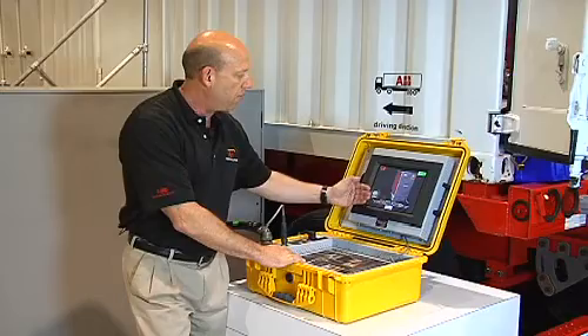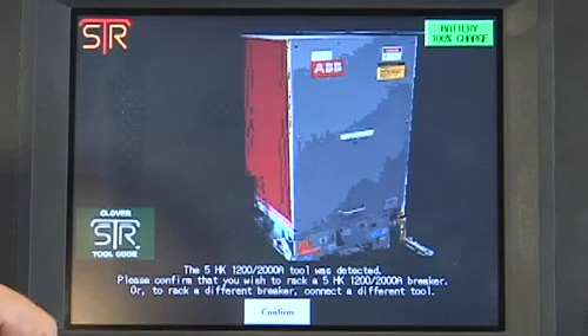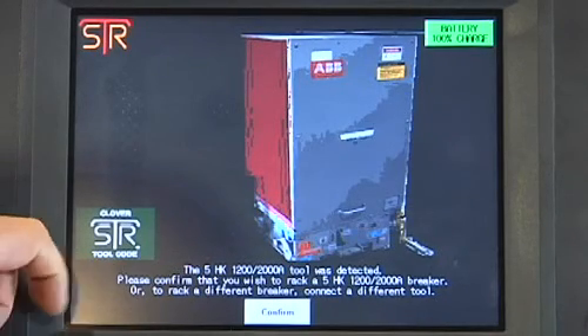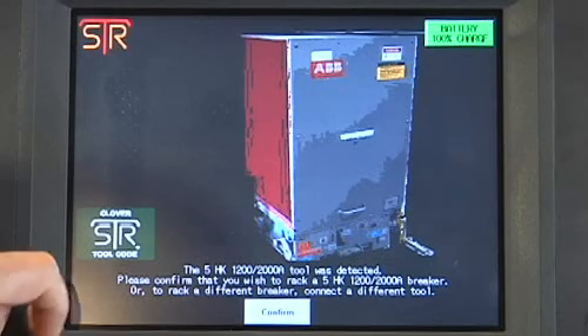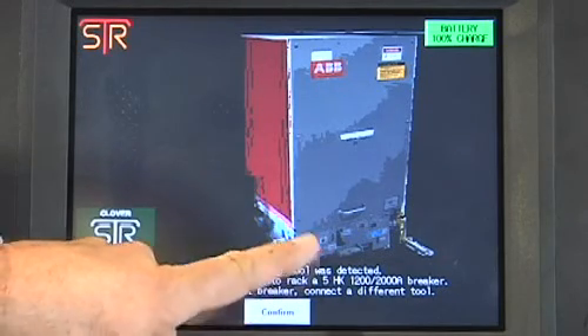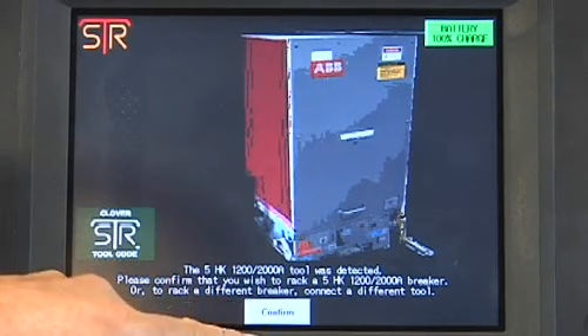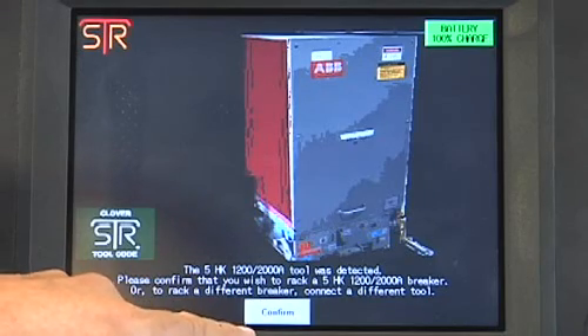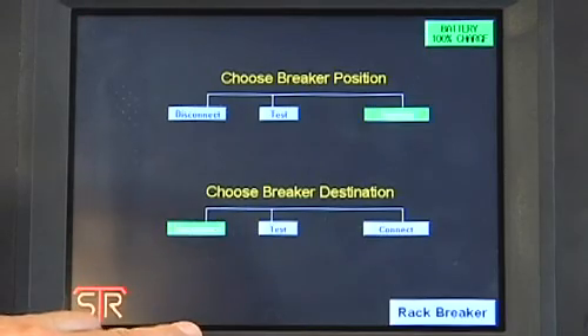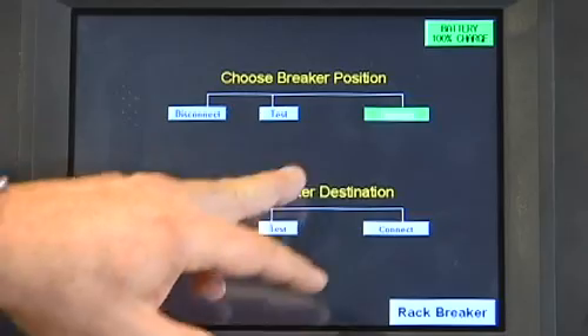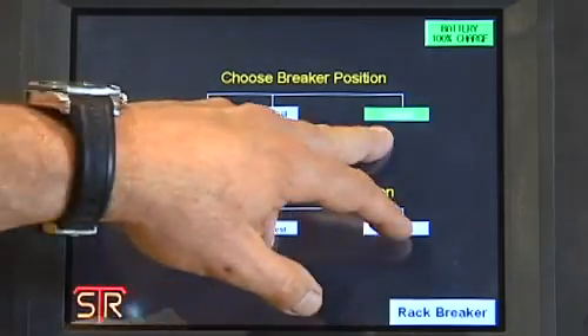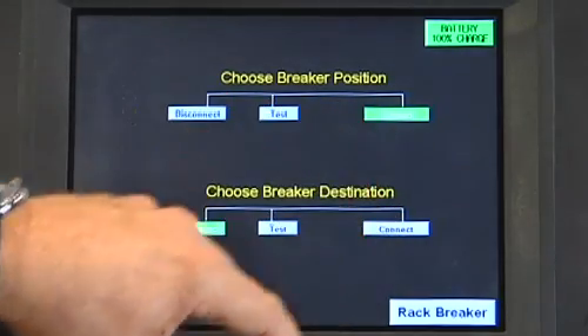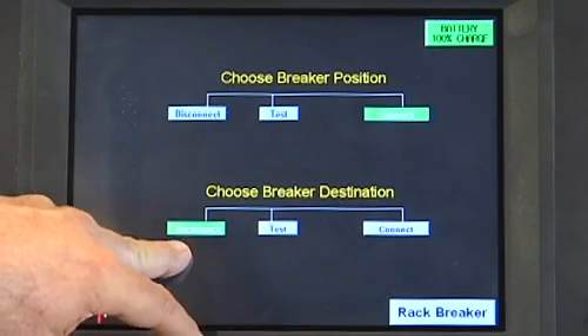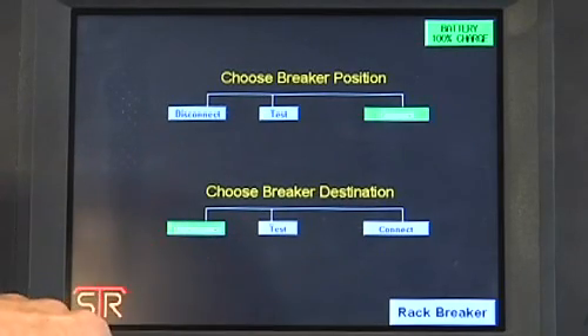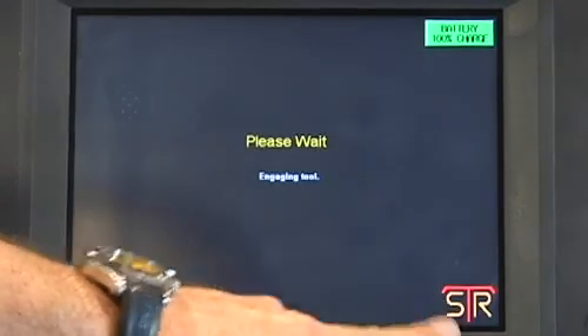Once we've confirmed that, it brings us to the screen acknowledging that we have connected the Clover application for the ITE 5HK circuit breaker. It gives us a text content, also an image of this type of circuit breaker, and we confirm that that's the breaker that we wish to rack. At this point, we select the breaker current position and our destination we wish to rack. And then we initiate by touching the rack breaker.